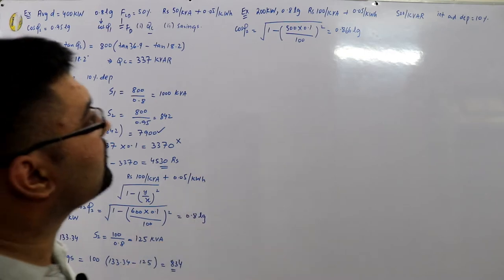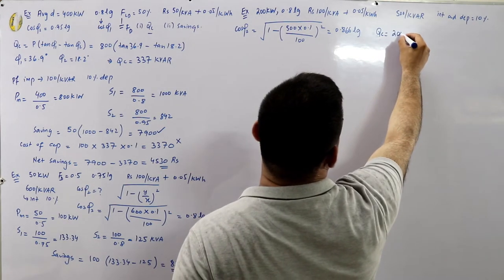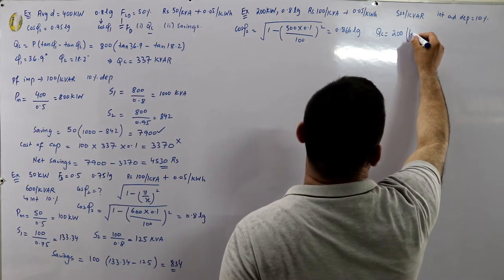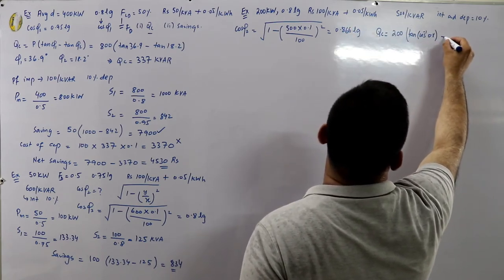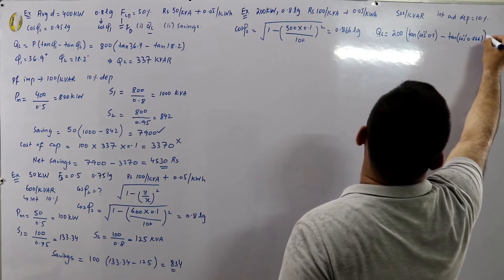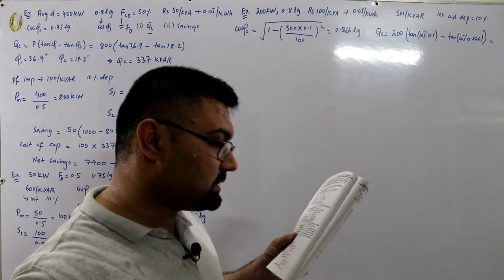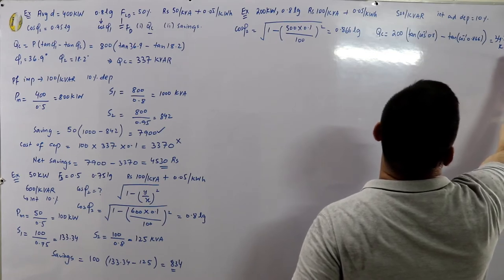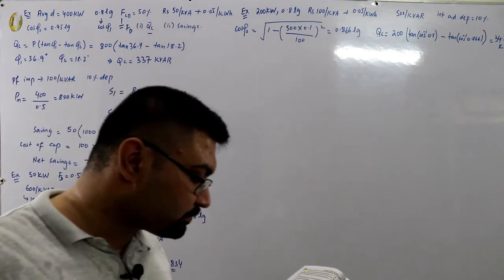Next, find the capacity of the phase advancing plant. Qc = P × (tan φ₁ − tan φ₂). P = 200 kilowatts (no demand factor given, so connected load = maximum demand). φ₁ = cos⁻¹(0.8) and φ₂ = cos⁻¹(0.866). The kVAr rating of the capacitors comes out to be 34.52 kVArs leading.